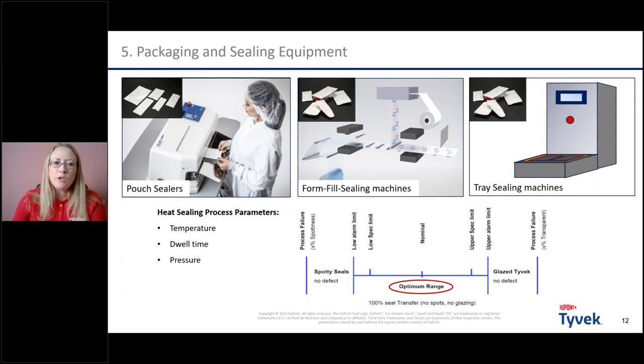For the blisters, flexible or rigid, you can use also form fill seal machines, or more automated machines. This roll hood, roll Tyvek and roll film, and then you have a filling station for the product, but highly automated. Or then you have the more manual tray sealing machines.